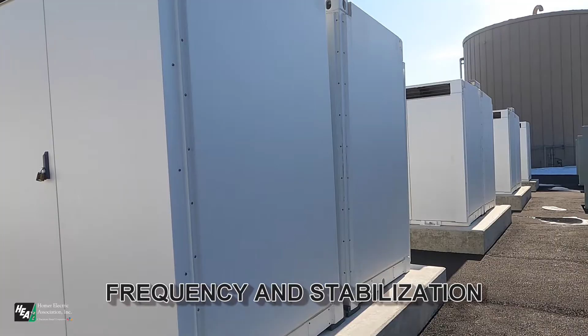Our focus is on regulation, which is the combination of frequency and stabilization. Stabilization is allowing the system to respond automatically to frequency deviations, which is where the challenges begin with non-firm renewable resources. The BESS will respond to frequency deviations much faster than our gas-fired units or hydro facility.